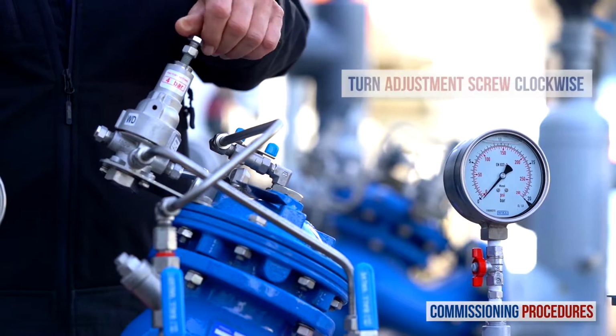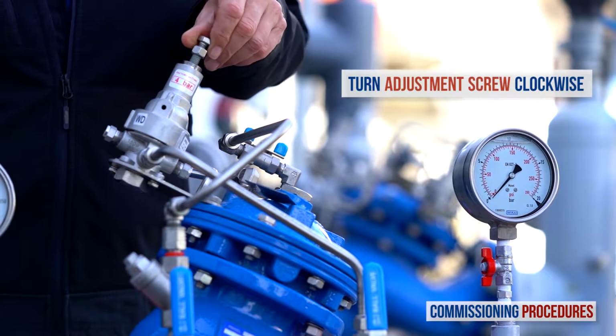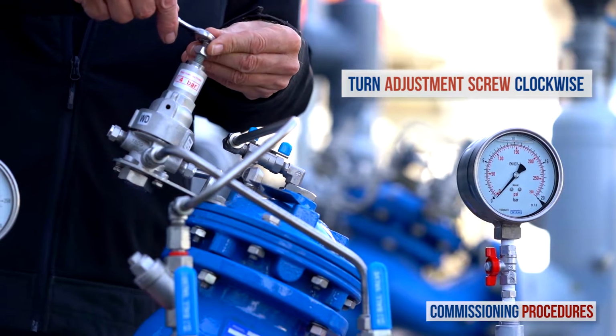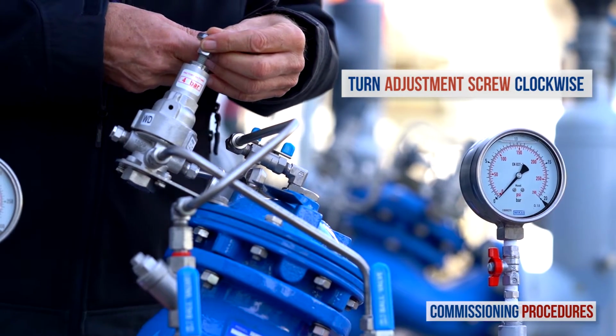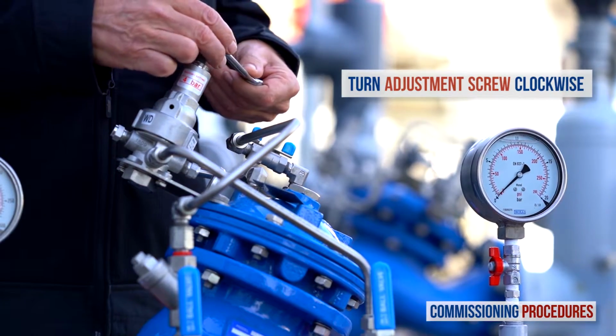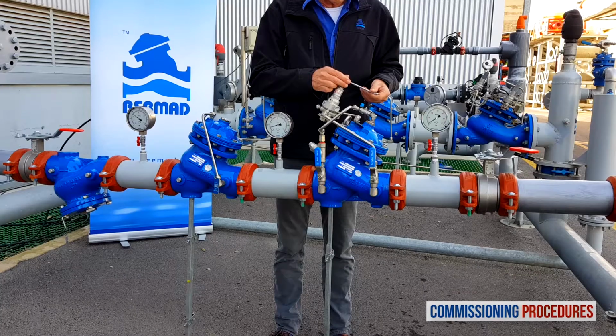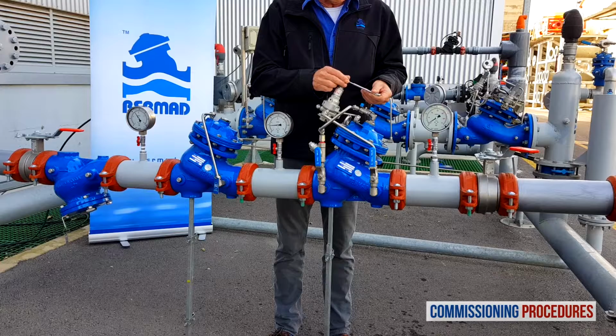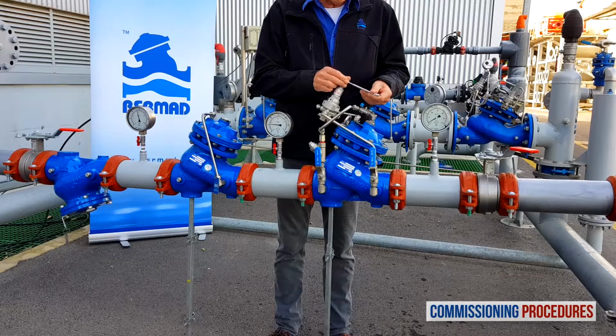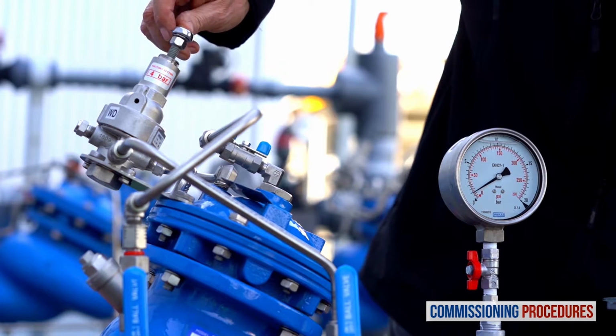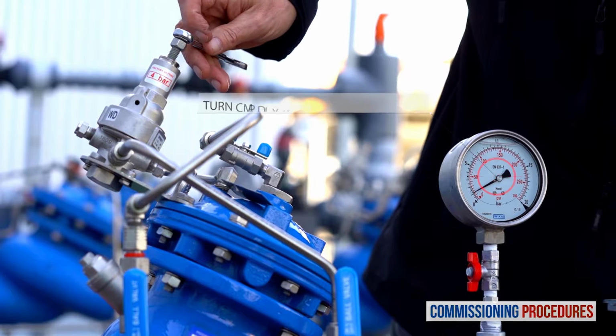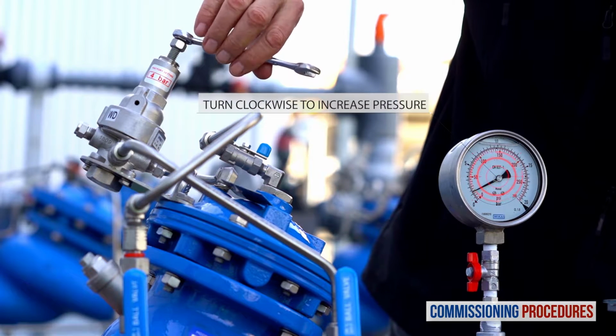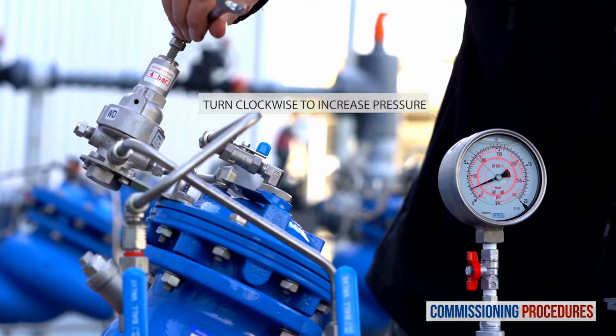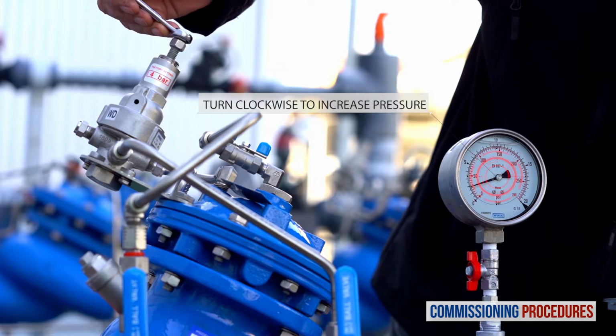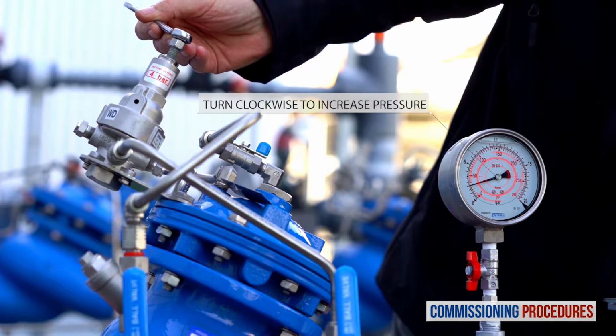Begin the pressure calibration process by slowly turning the pilot adjustment screw clockwise until you hear the valve opening or feel a resistance at the pilot adjustment screw. At this point, the secondary valve will start to open and fill the downstream consumer's pipeline. When the consumer's pipeline is full, continue to slowly turn the adjustment screw clockwise to increase downstream pressure, while monitoring the downstream pressure gauge until you reach the required pressure.